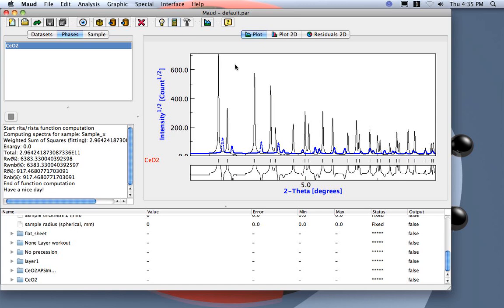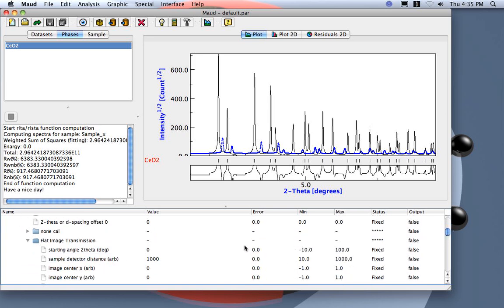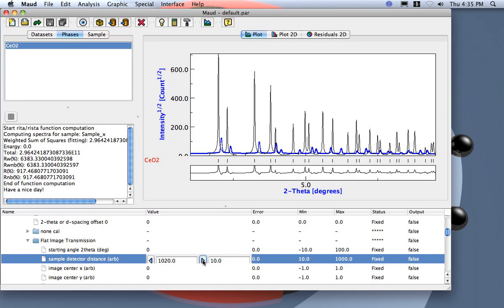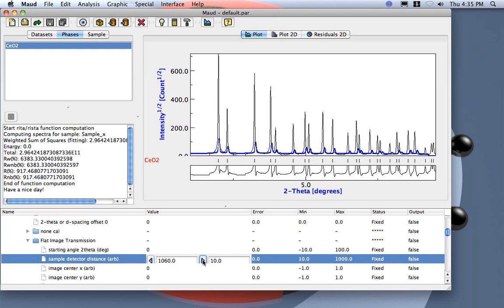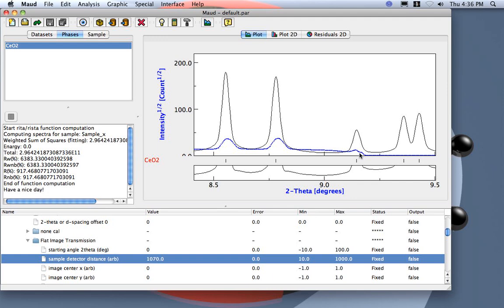Now let's compute the pattern to see if we have it correct. We do not have the correct distance — either the wavelength or the cell parameter is wrong. I think in this case the detector distance is what we have wrong. It should be a little more than a meter. Let's change it — increasing by increments — and it should be around 1070.